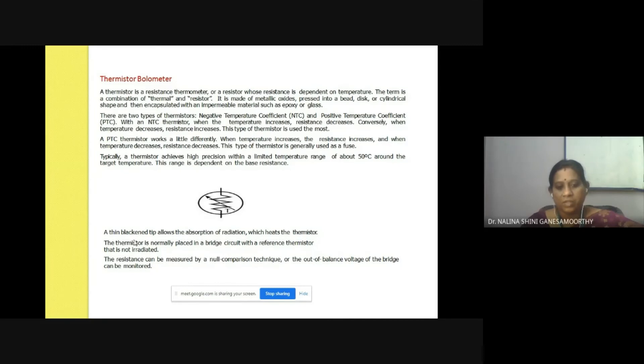Look at the diagram of this construction. A thin blackened tip allows the absorption of radiation which heats the thermistor. When the thermistor is placed in a bridge circuit arrangement, whenever the temperature rises, the unbalance of the bridge is detected.